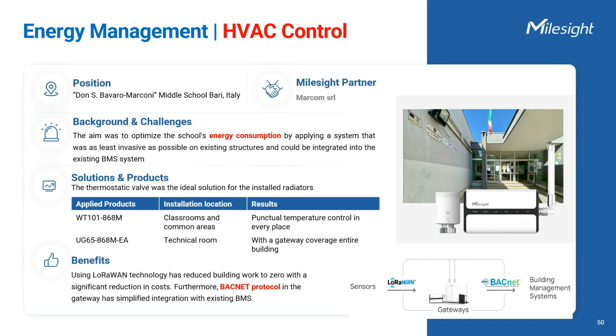In an Italian middle school, the Milesight WT101 smart thermostat was used to optimize energy consumption with minimal disruption. By installing thermostatic valves in classrooms and common areas, and a gateway in the technical room, they achieved precise temperature control throughout the building. Using LoRaWAN technology cut down on construction work and costs, and the BACnet protocol made it easy to integrate with the existing building management system.